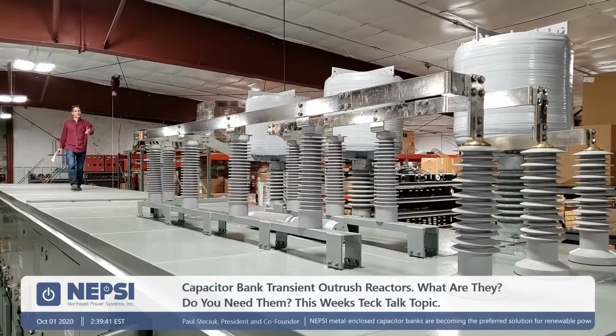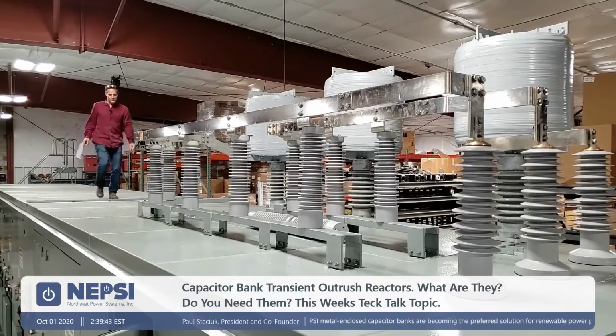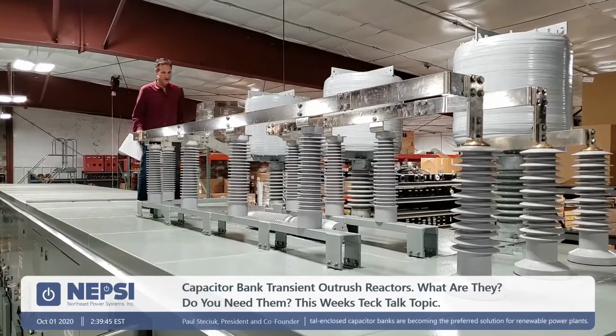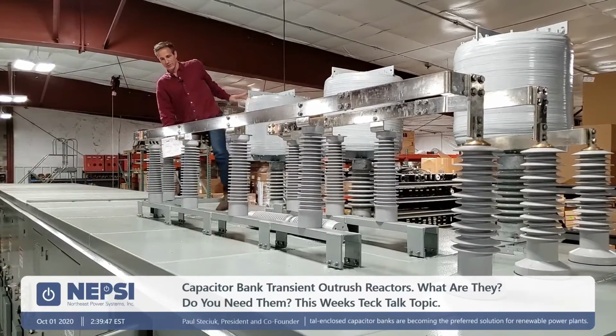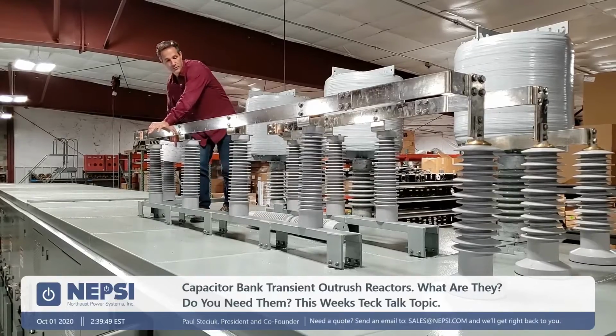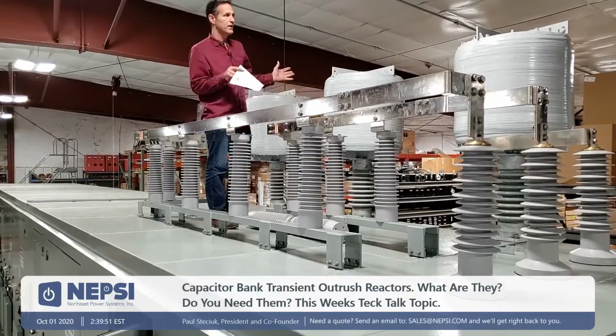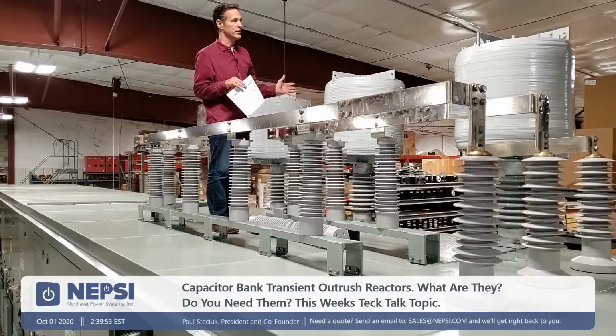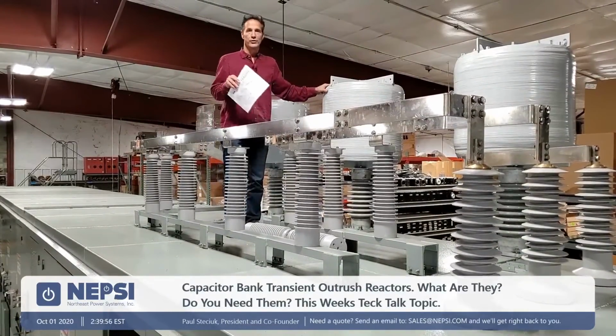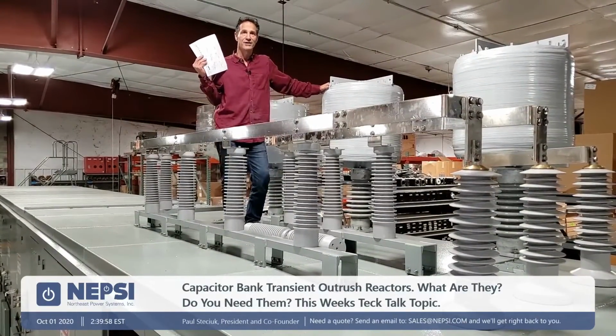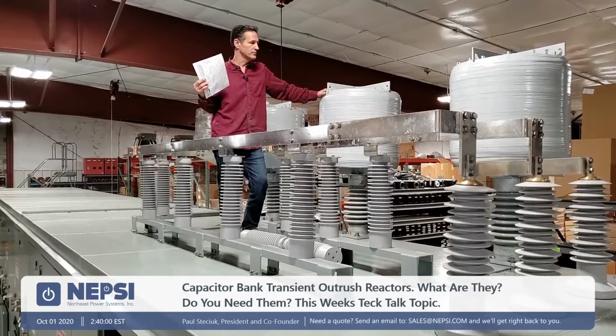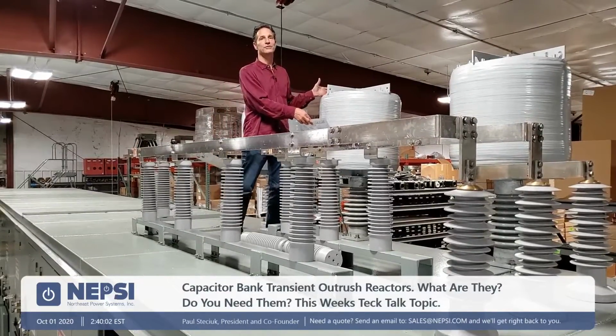All right, so you're looking at the transient outrush reactors here. And just to make sure I don't fall, I'm going to step between these main bus bars. So these are roof-mounted transient outrush reactors. You can see when we compare this to the transient inrush reactors that we were using for back-to-back switching, these reactors are much more substantial.